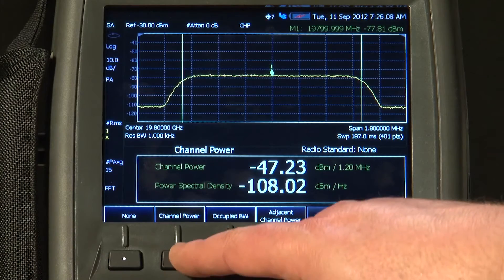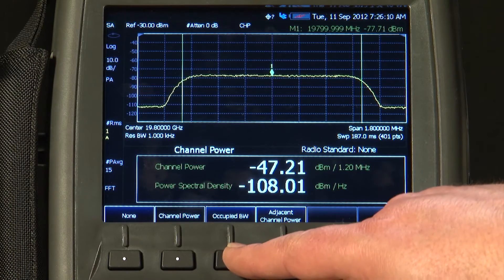If you are not sure what the channel power is of the signal that you are measuring, let us just go back to the channel measurements again, and this time I will select Occupied bandwidth.